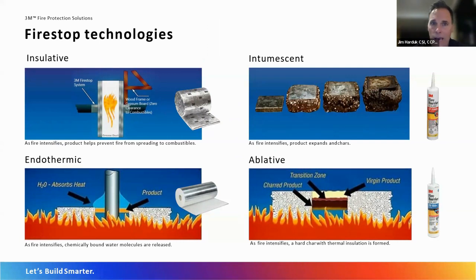But before I get into it, I just wanted to go through basically all the Firestop products are broken down into 4 distinct categories, and those categories are based upon the Firestop technology that those materials utilize. They are insulative, intumescent, endothermic, and ablative. So basically, the insulative products are a non-combustible material that we use to protect fire from spreading to combustible materials. Anything that falls into the intumescent category, when exposed to high temperature or fire, produces a very durable char. So basically, they expand and increase in volume.